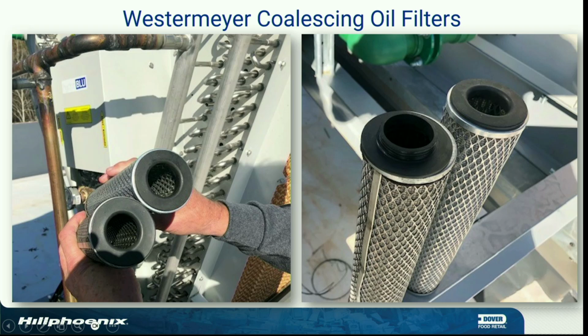So we also determined at the time that the sensor we were using, we've since changed it, was very sensitive. It went hypersensitive once it got out of the 80 degrees centigrade range. And that was what was causing that issue. It wasn't the pulse count, as was seen on some of the podcasts. It was not the pulse count. It was not the size of the oil valve. If you change that oil solenoid and put a 4 millimeter oil solenoid on there, there's not a 4 millimeter solenoid rated for 120 bars. Yes, sir. But I saw it on the internet. Yes, and everything you see on the internet's true, right?